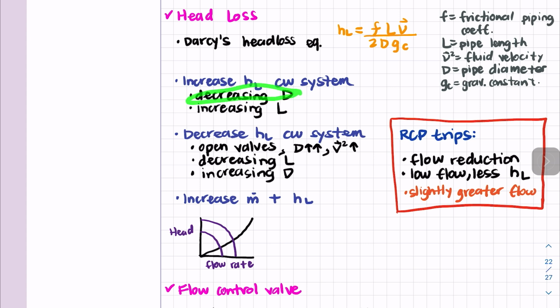So for instance, if we increase the head loss in a cooling water system, we either decrease the diameter or we increase the length. If we decrease the head loss in a cooling water system, we either open a valve, increase the diameter, increase the velocity, or decrease the length of the pipe, right? So we are basically playing with the length, the velocity, and the diameter here. Length, velocity, and diameter. Everything else stays the same. We don't use it.